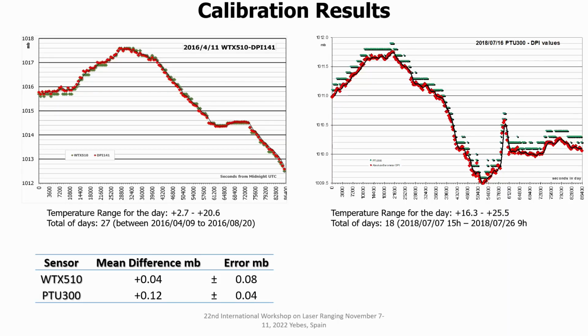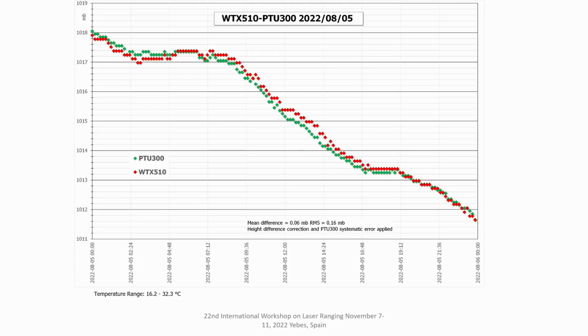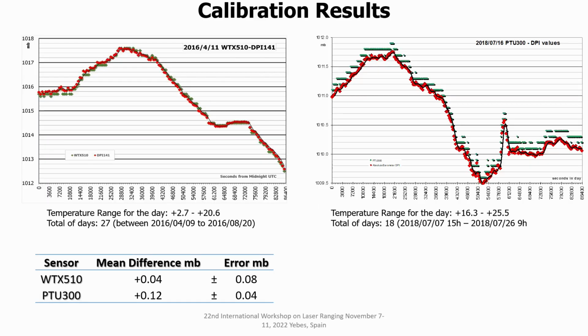Here are some sample results. On the left is one typical day from 2016, with a temperature range from 2.7 degrees up to 20. This plot shows pressure in millibars over one day, and you can see that the Vaisala WXT 510 versus this reference sensor matches pretty well as specified by the manufacturer - despite about 18 degrees temperature difference during the day, it matches quite well, with no systematics.